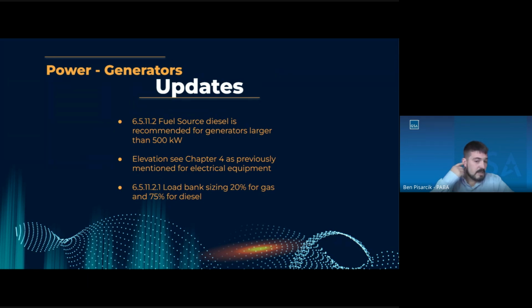Generators. This is a change here. Fuel source for diesel is recommended for 500 kW and larger. That previously said 350 kW. And again, it's recommended, not mandated.